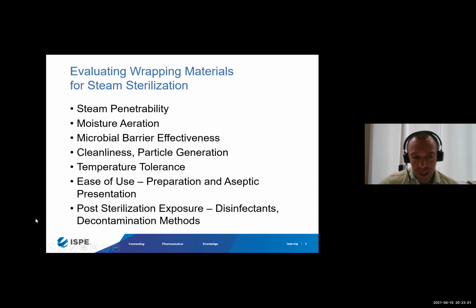Last point here is ensuring that the sterilization wrapping material is compatible with any disinfectants or sporicides that might be used to decontaminate the surface of the sterilization wrapping as it's moving through your cleanroom facility. For example, if your autoclave is emptying out into an ISO 6 grade clean room and the storage room is an ISO 6 class, perhaps the filling line is in an ISO 5 grade clean room, that transition from the ISO 6 to the ISO 5 needs to have a surface decontamination done to the sterilization wrapping.